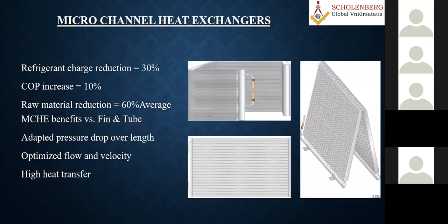Now, this is what I was telling, the product design, particularly the heat exchanger. If you see the refrigeration circuit, this micro-channel heat exchanger is another upcoming technology, which I attended an online course on 3 or 4 years ago. What are the benefits of micro-channel heat exchangers, particularly in air-cooled systems, air-cooled condensers, and all these unitary package units? The refrigerant charge is reduced almost 30%, because mass flow of the refrigerant is very, very important. If you say about 200 tons or 300 tons, a huge amount of refrigerant you are going to charge. That refrigerant is also very expensive.